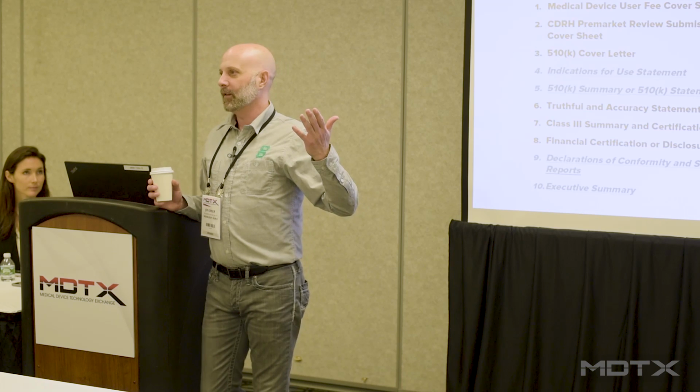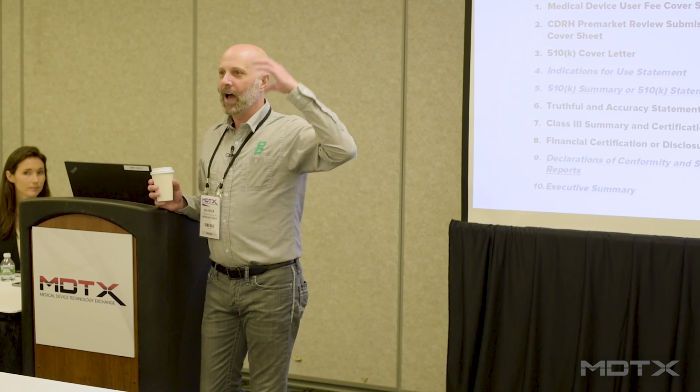510K summary, you're summarizing what it is that your product is all about. And so, granted it may be high level, but there's some information from a design control perspective, like some of the safety testing that we've done and that sort of thing, that is going to find its way into that 510K summary. Declaration of conformity and summary reports. If I do electrical safety testing for IEC 60601, that is a design verification activity that I'm going to declare that I'm conforming to that standard. If I do biocompatibility per ISO 10993, that is a design verification activity that I'm demonstrating that I'm safe, right?